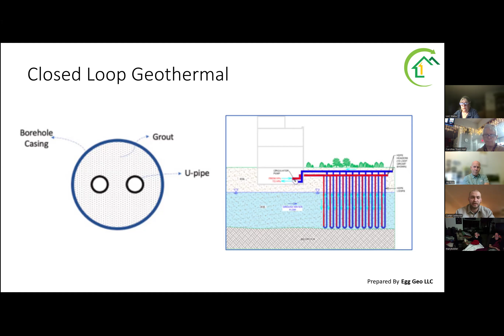This is the submerged closed loop heat exchanger. It operates on the same principle as an open loop, where you take water out of the ground and put it back into the ground after a heat exchanger. However, your production well and injection well, instead of being separated geographically or horizontally, are separated vertically. There's a heat pump installed between two perforated sections of the pipe. So in the diagram, water can come in and out of two sections of the pipe based on the season.